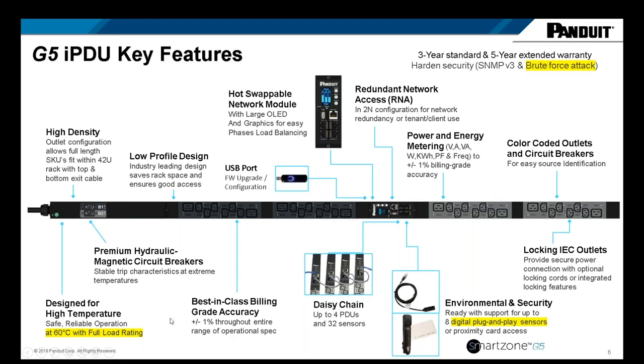One last related point—I mentioned earlier how our Gen 3 product was rated at 45 degrees C. We saw some competitive products rated at 45 degrees C that would then claim 50 or 55 degrees C, but that's basically creative marketing, because what they were effectively doing was derating the product by 50%—meaning you can't use all the outlets you paid for if you run at those higher temperatures.